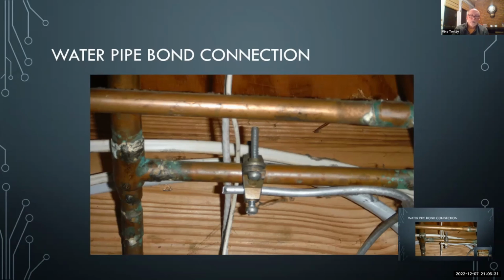You'll see this one is aluminum. I didn't mention it a while ago, but the grounding electrode conductors you're going to see are typically copper, because the code says you can use aluminum, but it can't be within 18 inches of the ground. So people don't use it. That's kind of hard to do, going to the ground rod like we showed in the pictures earlier and staying 18 inches away. So the grounding electrode conductor, GEC, is generally copper. Now this is aluminum, this is a water pipe bond, and that's fine. It goes back to the service panel, and it can tie into the grounding electrode system at any point to bond that water pipe.